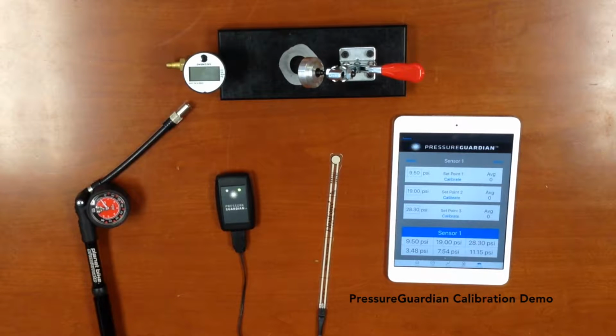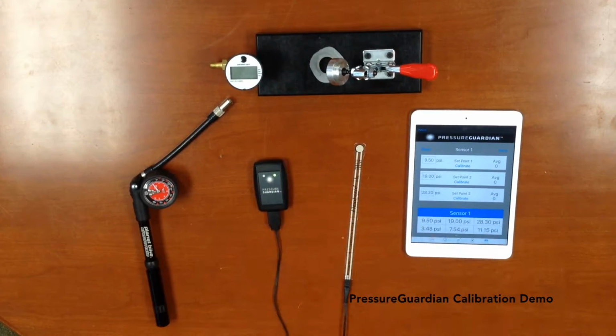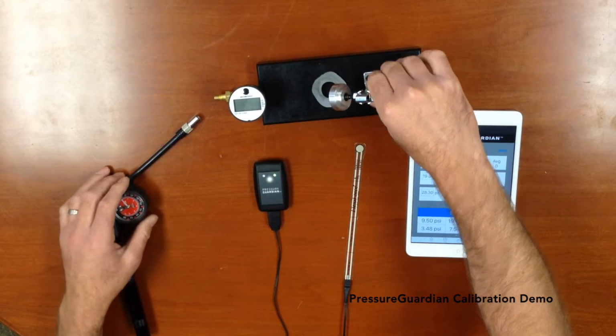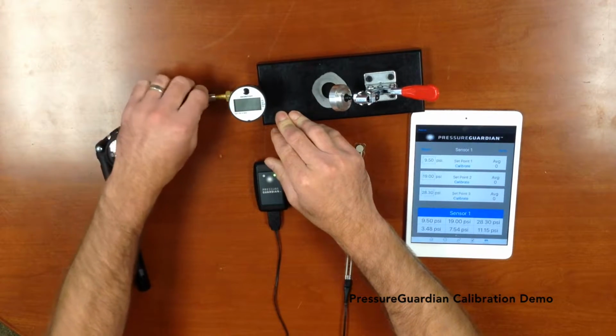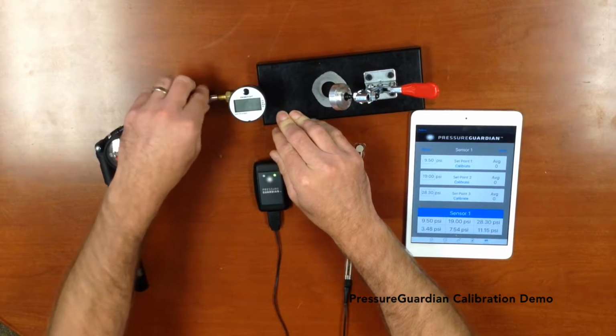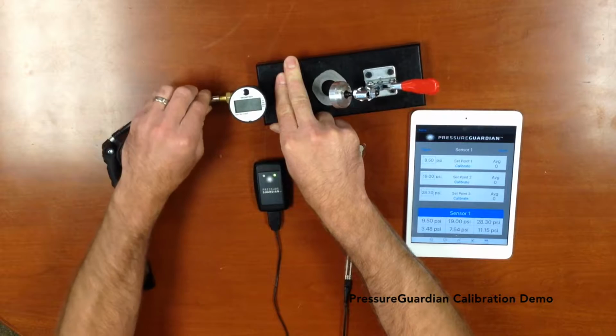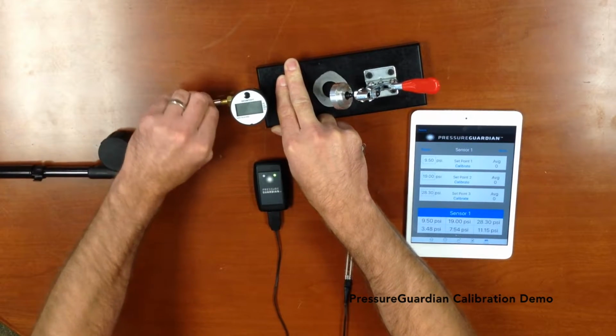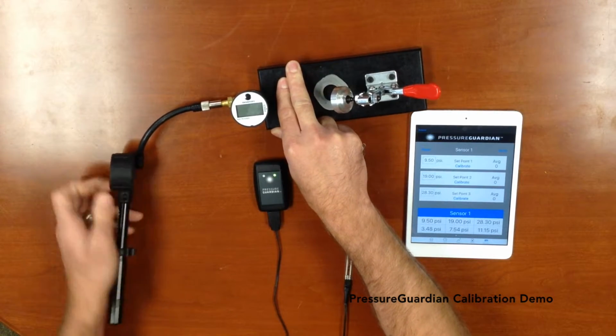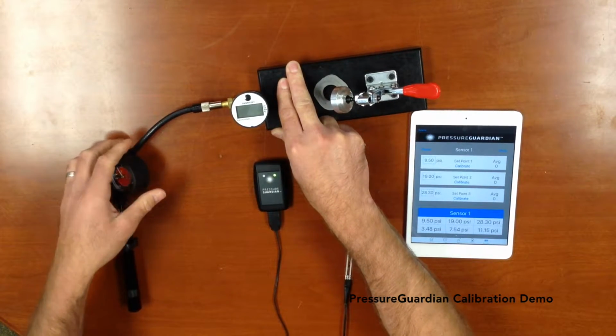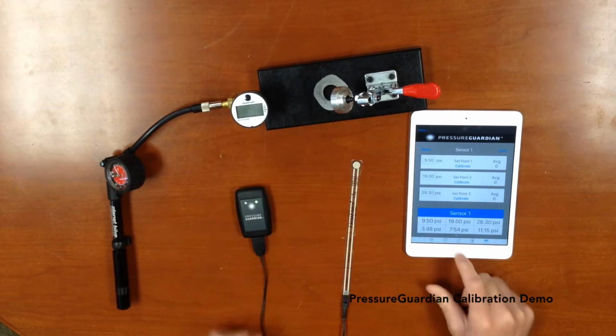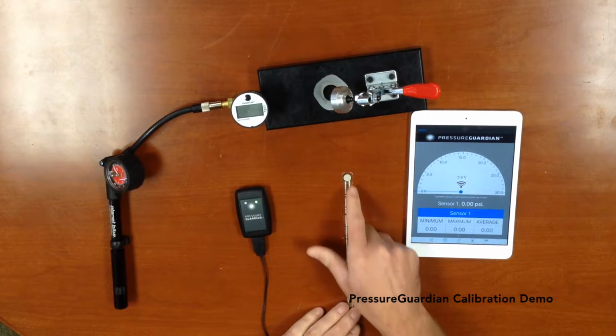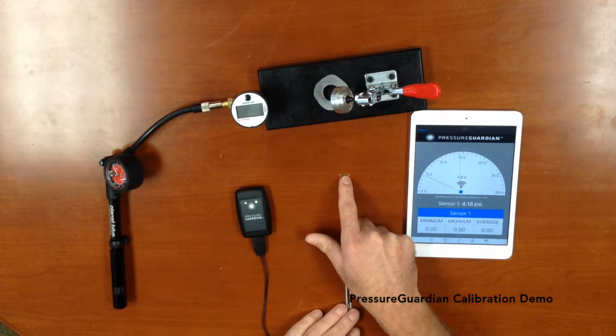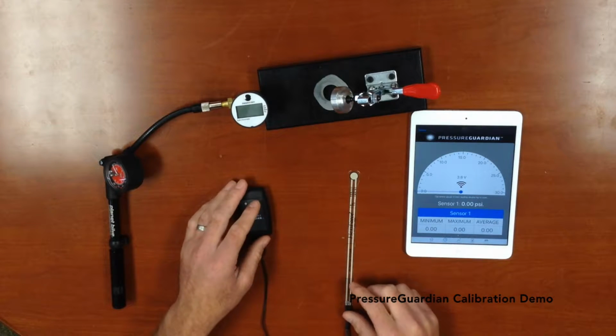Today we're going to share with you how to calibrate the sensor for the PressureGuardian system using the PressureGuardian calibration jig. Initially we're going to take the calibration jig out of the package and hook up the pump to the calibration jig. We want to make sure that this pump is securely fastened on the end of the jig. Once that's securely fastened, we will ensure that the sensor is working and the PressureGuardian is linked to the module.